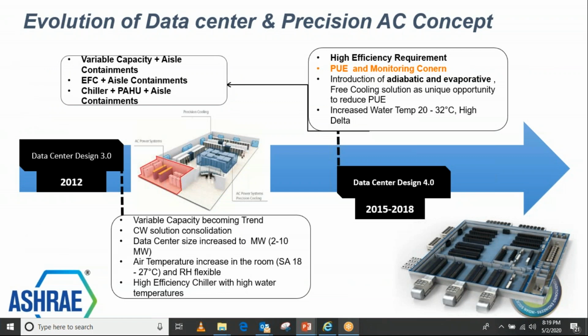So this made change in the industry. This changed the way the manufacturers like Vertiv or many other suppliers, Schneider or anyone in the market, started thinking that they must use a system which should be able to deliver higher supply and higher return air, and at the same time concepts like aisle containments, like hot aisle or cold aisle containment kind of philosophies started coming in the market.